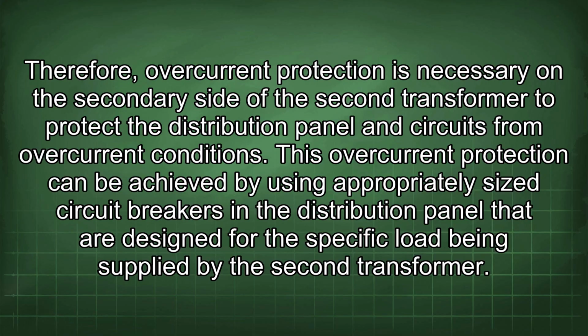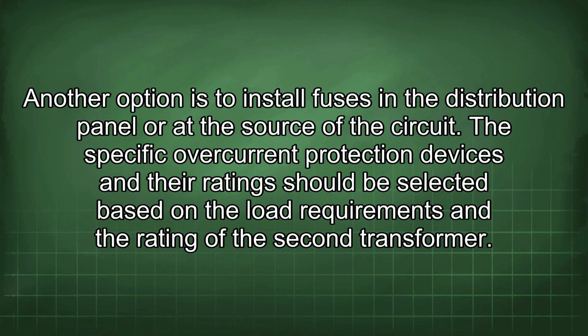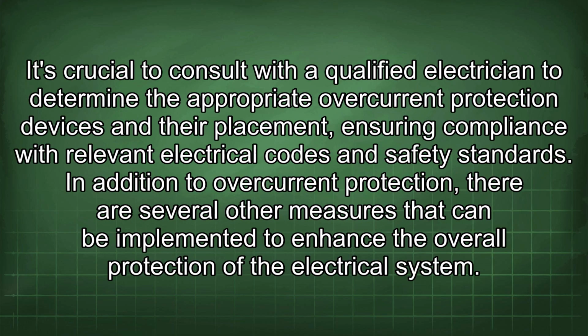from overcurrent conditions. This overcurrent protection can be achieved by using appropriately sized circuit breakers in the distribution panel that are designed for the specific load being supplied by the second transformer. Another option is to install fuses in the distribution panel or at the source of the circuit. The specific overcurrent protection devices and their ratings should be selected based on the load requirements and the rating of the second transformer. It's crucial to consult with a qualified electrician to determine the appropriate overcurrent protection devices and their placement, ensuring compliance with relevant electrical codes and safety standards.